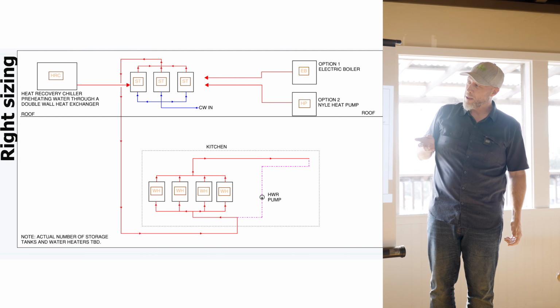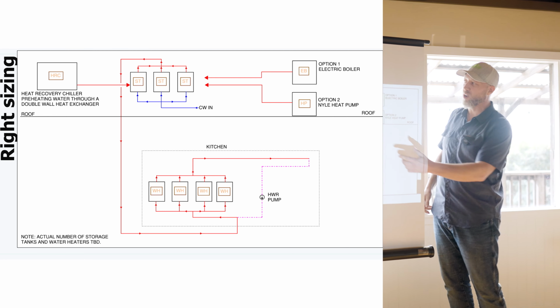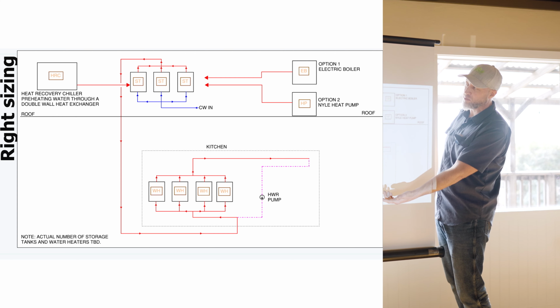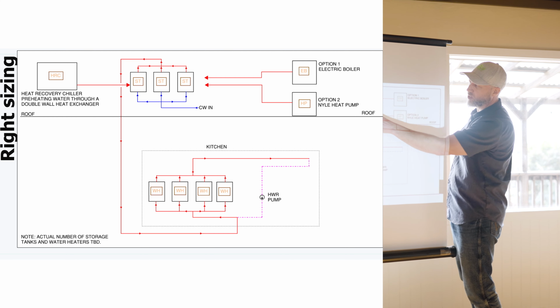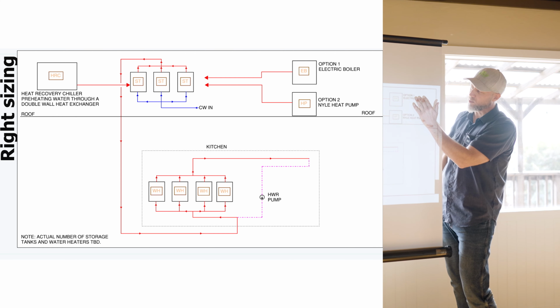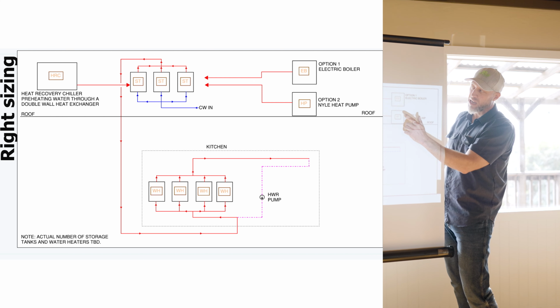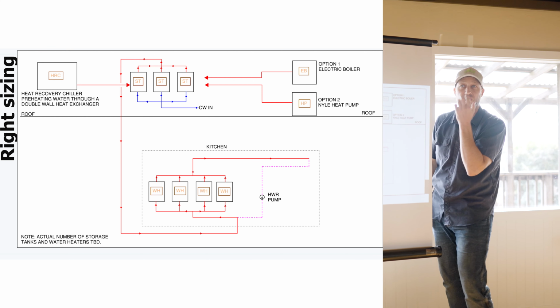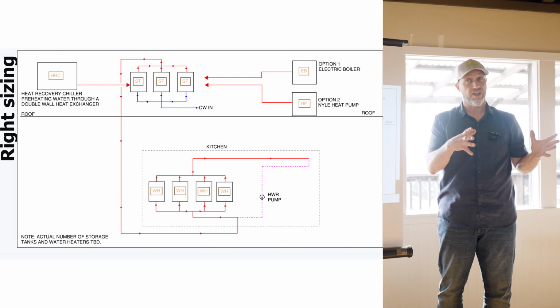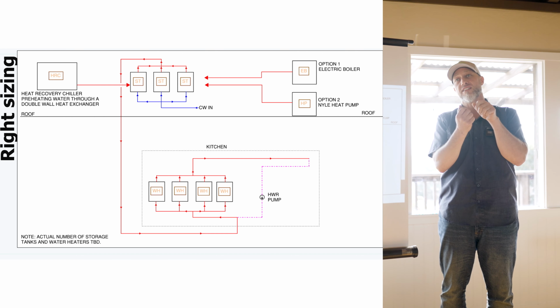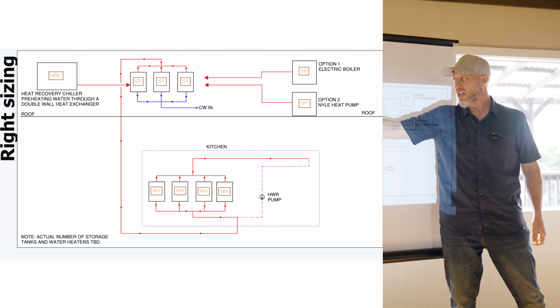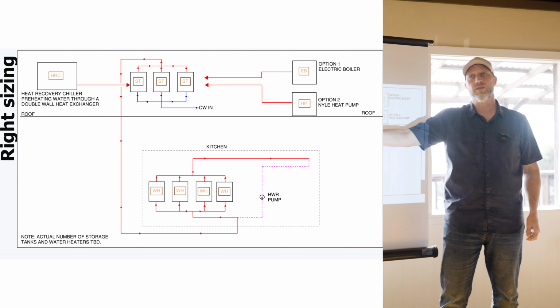So there's a lot of complexity here, but the way it's going to end up going is we've got storage on the roof, backup resistance with a heat pump, but there's also a heat recovery chiller in the plan too, because there's a giant server load, so there's all this waste heat coming off the heat recovery chiller. So we're going to preheat with the heat recovery chiller.